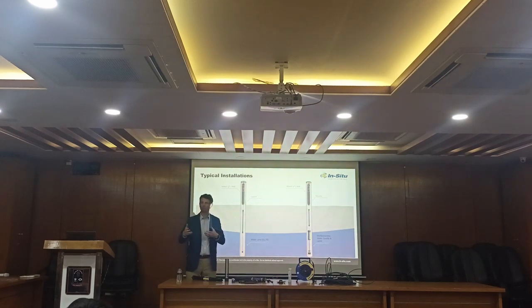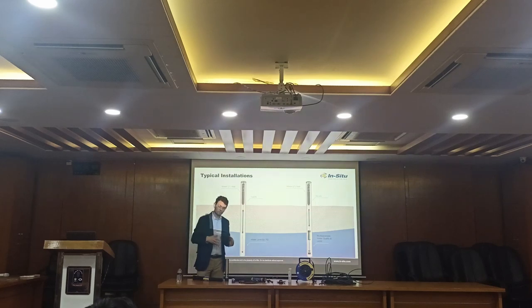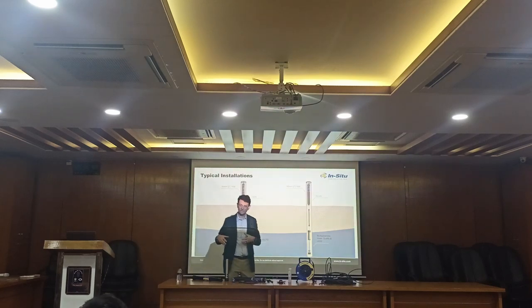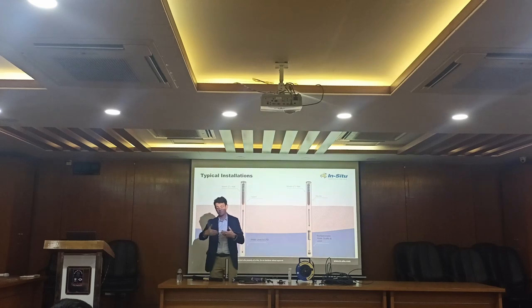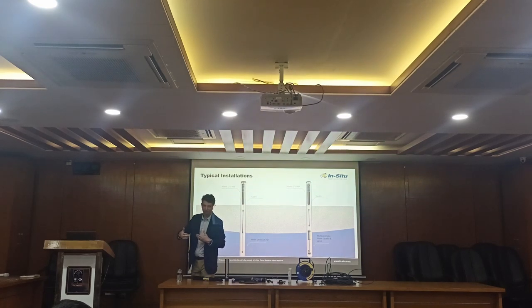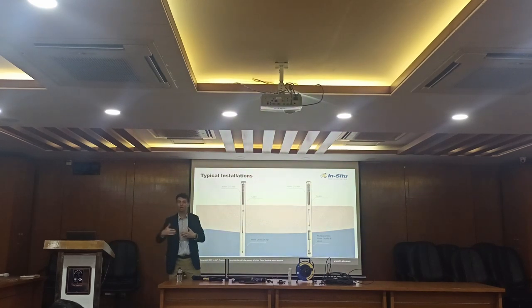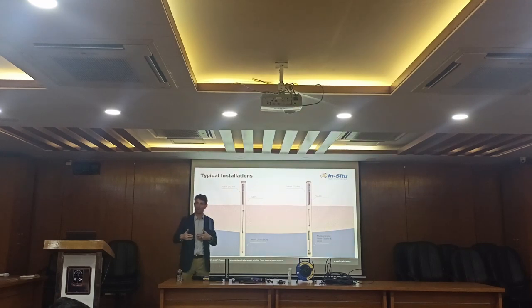The question that came up: if I'm doing long-term monitoring, why would I have long-term monitoring for pH if I have to go out every month anyway and calibrate? Maybe it's not worth it. Well, one advantage with some of the sensors we've designed is they potentially can have a much longer calibration period. Now, it depends on your water and your application - I'll stress that, you may still have a shorter life depending on how you're using it.